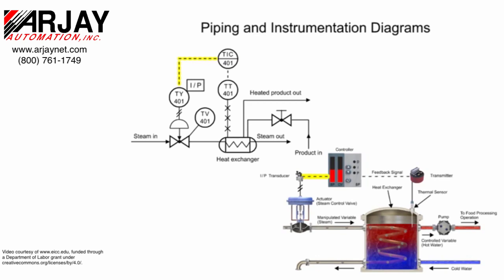An electronic signal from the controller is indicated by the dashed line. The controller output is connected to the transducer that controls the steam flow indicated by the second letter Y of the functional identifier.